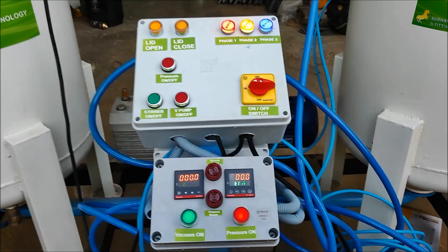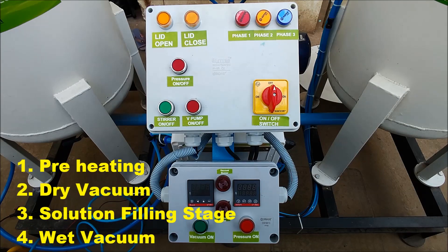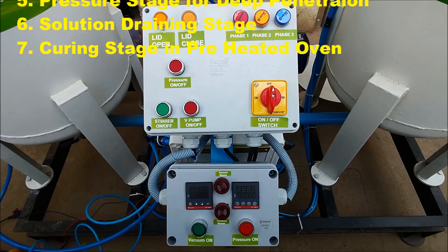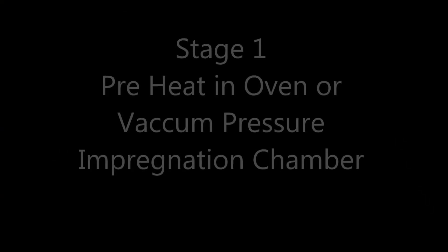The 7 stages of VPI are: preheating, dry vacuum, solution filling stage, wet vacuum, pressure stage for deep penetration, solution draining stage, and curing stage in preheated oven.